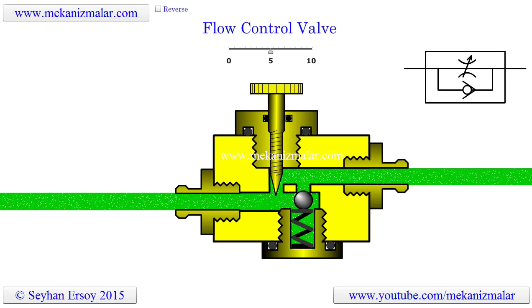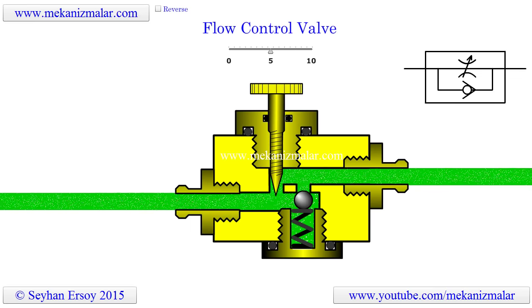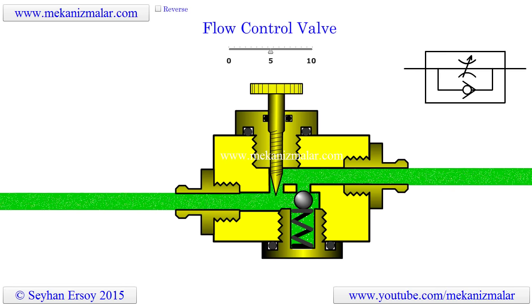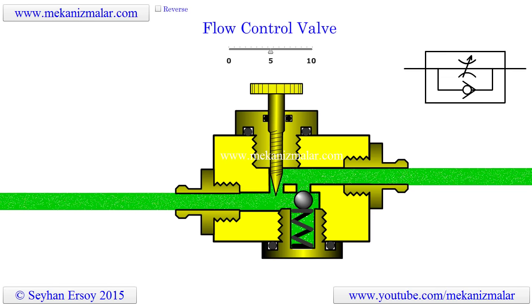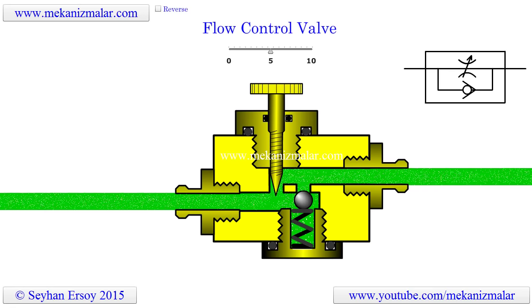Welcome to the video tutorials of Mechanisms by Mekanizmalar. In my previous video the working principles of a needle valve has been explained. One of the biggest shortcomings of the needle valve is that it restricts the flow rate in both directions. When you use a needle valve for speed control of a piston of an air cylinder in forward motion, it will also restrict piston motion in the return stroke.